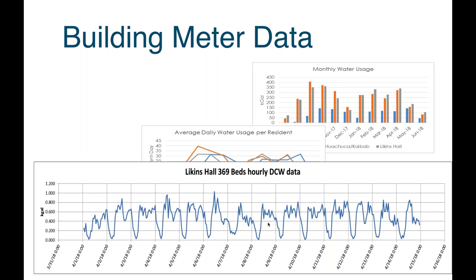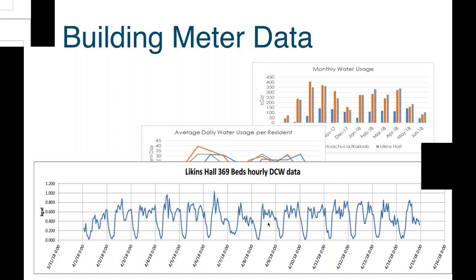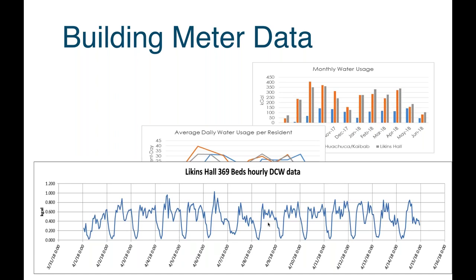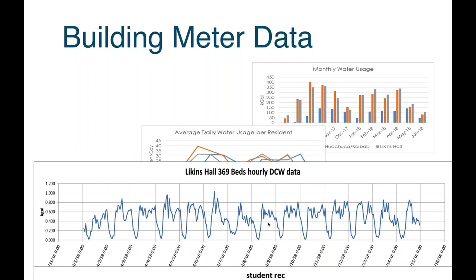So that's actually hourly data. That is great for tracking leaks and anything happening inside the facility. We've seen cases where you first look at the monthly data and notice a building behaving differently one February versus the last, then you dig into this level of detail and see why: there's a valve not closed, there's a leak, and you can really see it hour by hour in this data set.